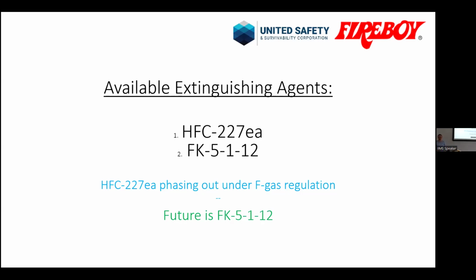So that's why lots of boat builders or service agents have now swapped to FK 5-1-12, which is a similar chemical category. It's a clean agent as well, but it's got a bit more of a green tick to it. It's got a lower global warming potential. So when released, it remains in the atmosphere for a very short time, so it doesn't affect the Earth so much as, for example, HFC, which does have quite a high global warming potential. So lots of the manufacturers, including us, have moved away from HFC.